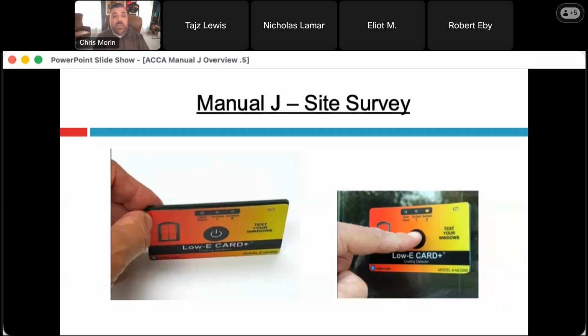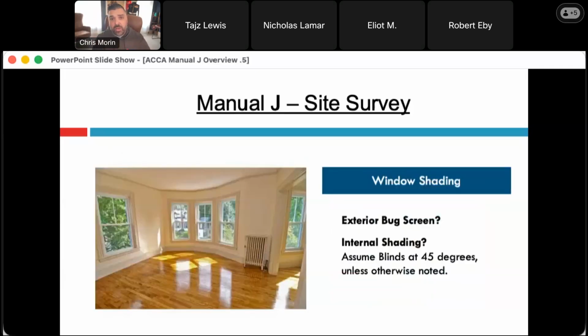And it really helps, if you're doing a site survey, to make sure whether the window has a low E coating or not. I've seen this impact the heat loss and the heat gain by 10 to 15%, depending on the number of windows and the size of the glass. I personally use this low E card from EDTM. It's very low cost. I think they make 2 different versions of it. Might be $100, but super useful to make sure I know if there's one film for low E or if both of those panes have a film, if both are coated with low E.